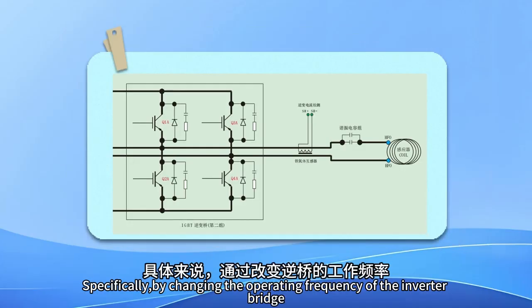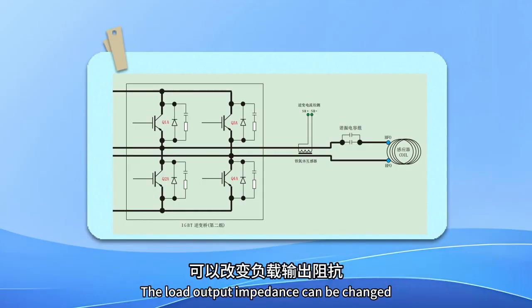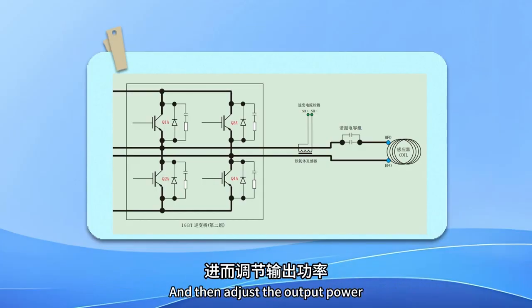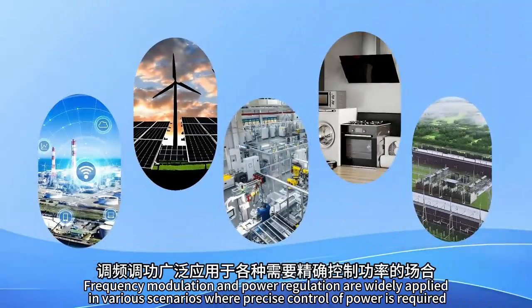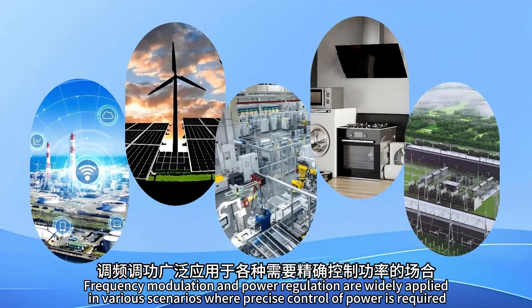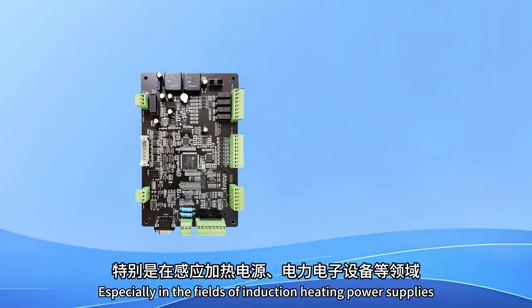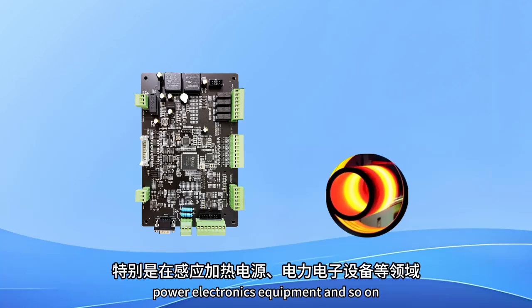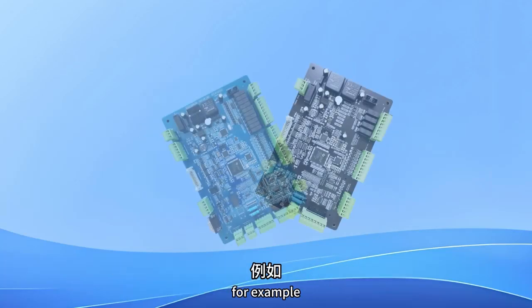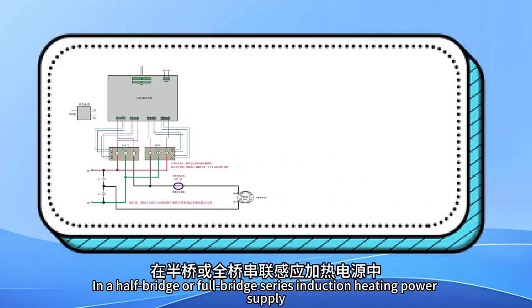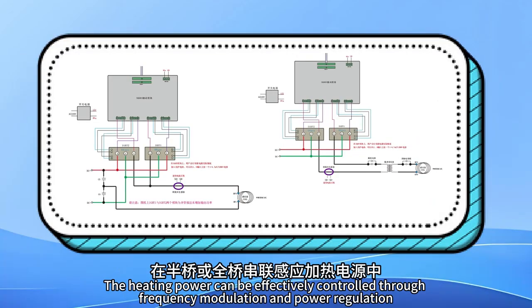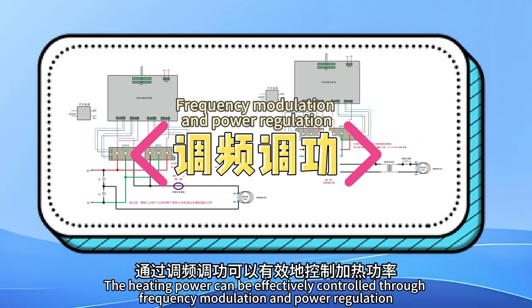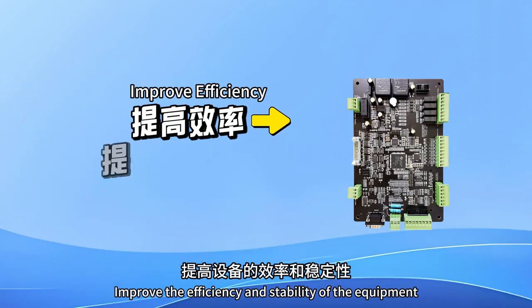Specifically, by changing the operating frequency of the inverter bridge, the load output impedance can be changed, and then adjust the output power. Frequency modulation and power regulation are widely applied in various scenarios where precise control of power is required, especially in the fields of induction heating power supplies, power electronics equipment, and so on. For example, in a half-bridge or full-bridge series induction heating power supply, the heating power can be effectively controlled through frequency modulation and power regulation, improving the efficiency and stability of the equipment.